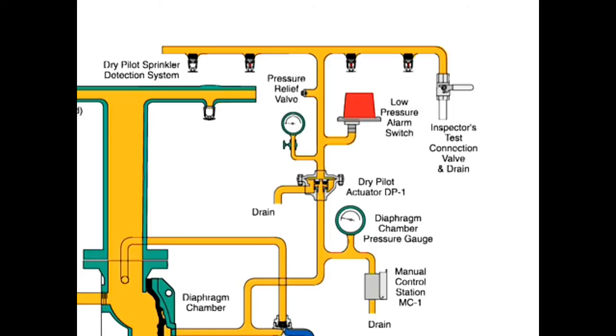Reset the dry pilot actuation system by replacing operated pilot sprinklers and re-establishing dry pilot pneumatic pressure.